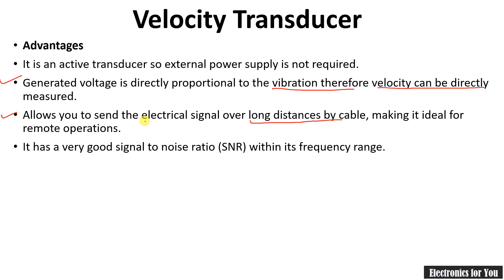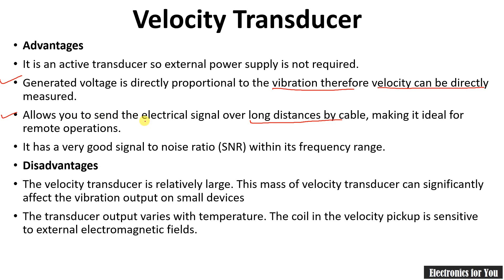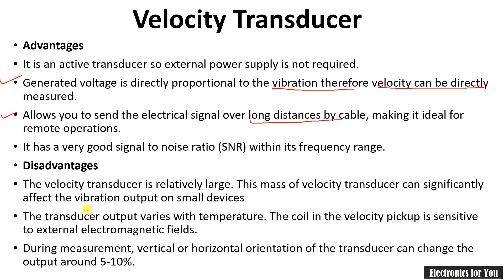The disadvantages of the velocity transducer: it is generally mounted on the target surface itself, so if the target surface is small, the weight of the transducer will affect the vibration, potentially giving wrong output. The transducer output varies with temperature. The coil in the velocity pickup is sensitive to external electromagnetic fields. During measurement, vertical or horizontal orientation of the transducer can change the output by around 5 to 10 percent.